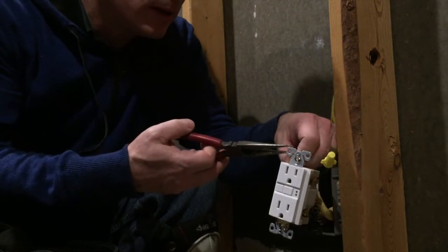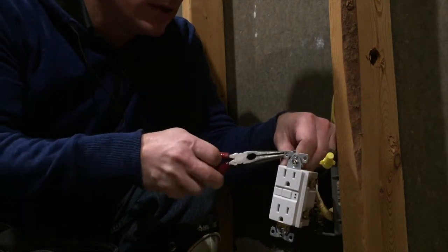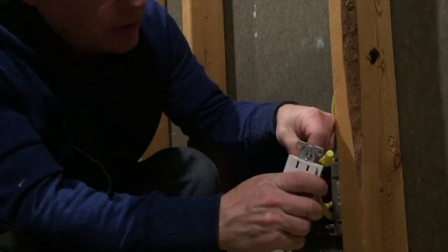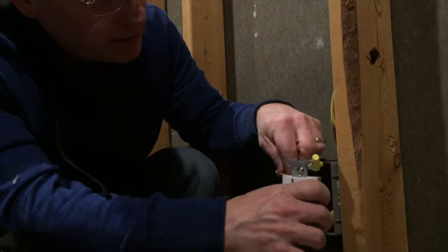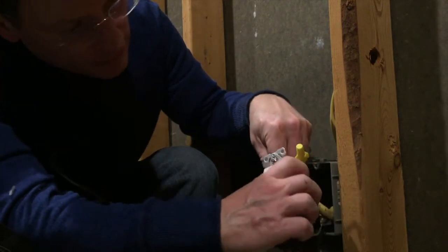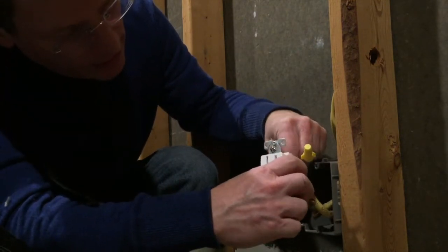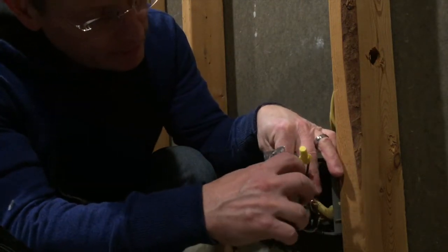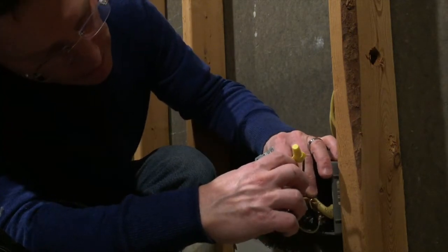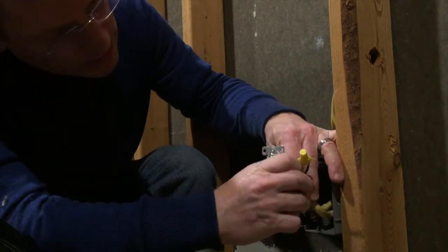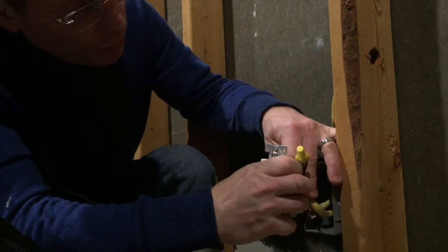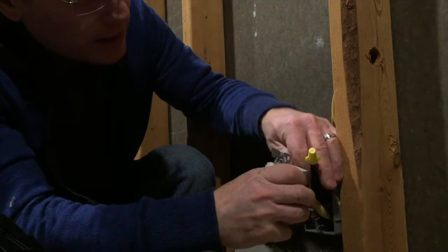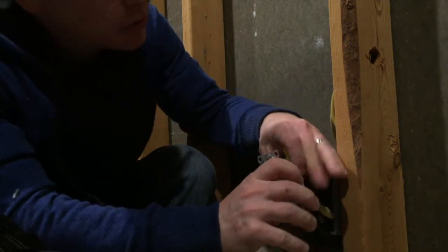I'm going to disconnect the middle outlet, and then I'll know if the short circuit is in the first 3 outlets or the last 3 outlets, and then I can narrow it down and work towards isolating the outlet that has the short circuit or the span of wire that has the short.